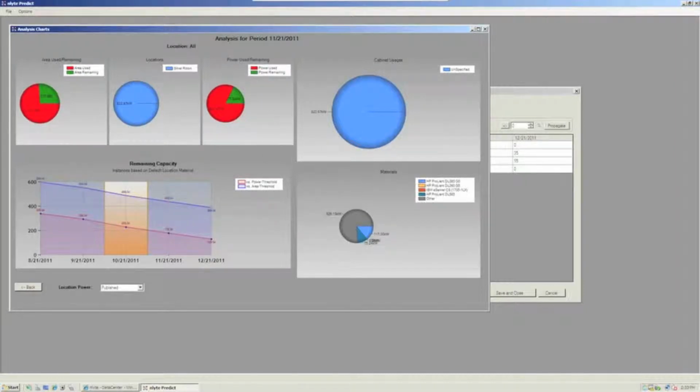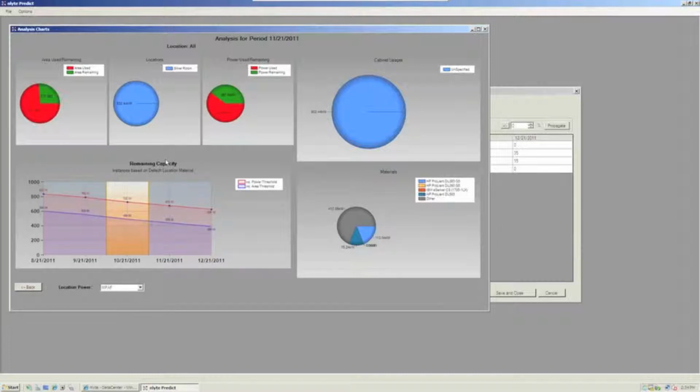This initial run was using the published power specs. So maybe I'd rather use that derated power spec, where we lower that huge startup power that the manufacturer lists. So I can bring that down and look at it at a more realistic value. Or, if you're a very efficient data center and you've actually got that real time data, I can peek at it and look at it that way.